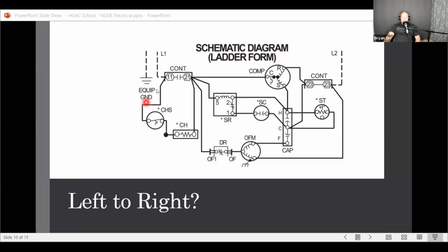Another thing is that when you have a run winding, for example, here, and you have the crankcase heater, the reason the run winding doesn't really get that hot is because the windings in your compressor are actually pretty low resistance. I've had this happen a bunch of times, and I've mentioned this on several podcasts, so forgive me if I've already said this so many times. When you measure from leg to leg on a compressor, say run to start, then start to common, run to common, those are going to be very low resistances.